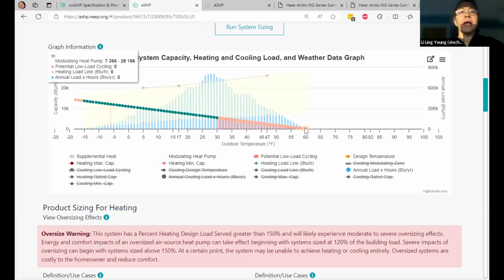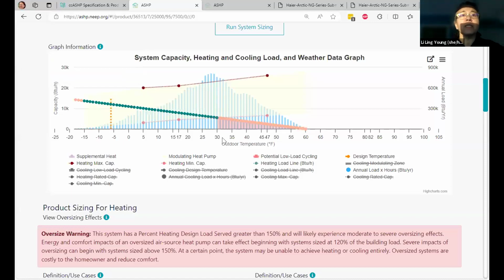Instead, it's going to short cycle. Remember my discussion of part load efficiency? This is the part load condition, not anywhere near our design conditions. For a large part of these part load conditions, the equipment can't modulate—instead it short cycles, and that hurts efficiency. So we'd expect poor efficiency across this range, right up until this point, where the heat pump can finally settle in and run continuously to meet the load.